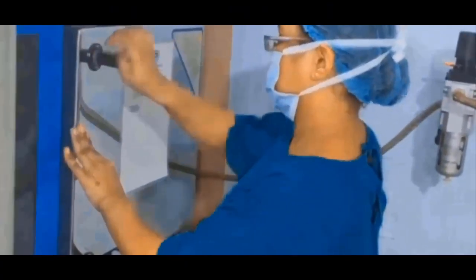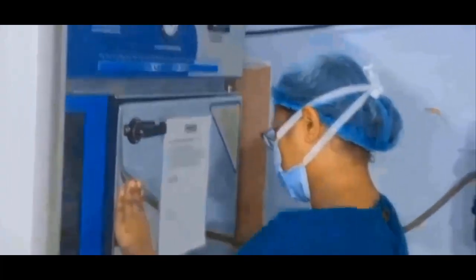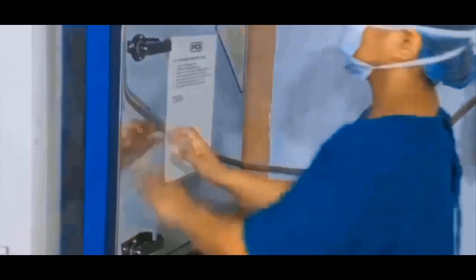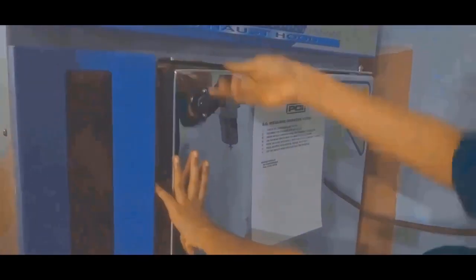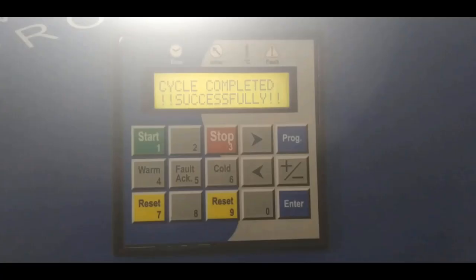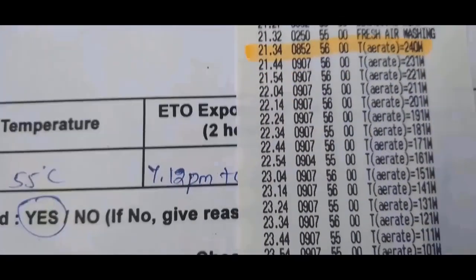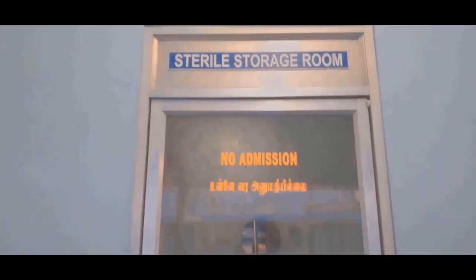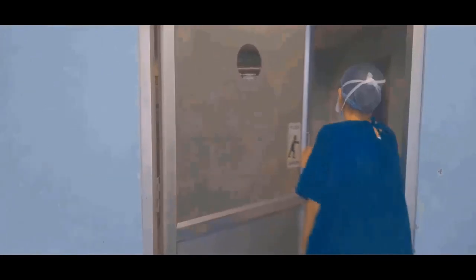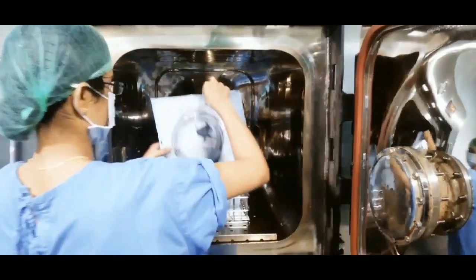After the temperature has reached 55 degrees Celsius, press Process Start mode. Check whether the process printout is available. After the process is completed, it will show cycle complete on the display, which is approximately 7 hours and 30 minutes. Ensure that the printout is verified by the CSSD person. Open the sterilizer door and check the change of color in the indicator sticker. Color must change from blue to green, indicating adequate sterilization.